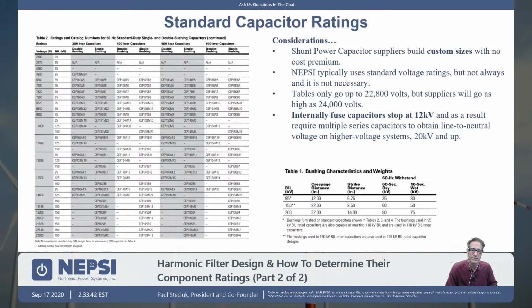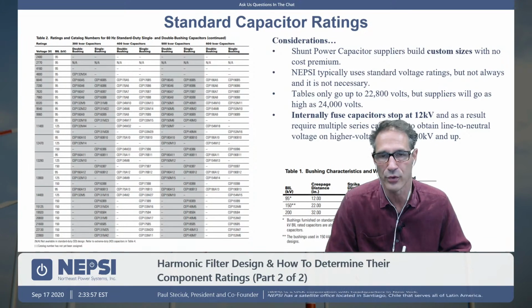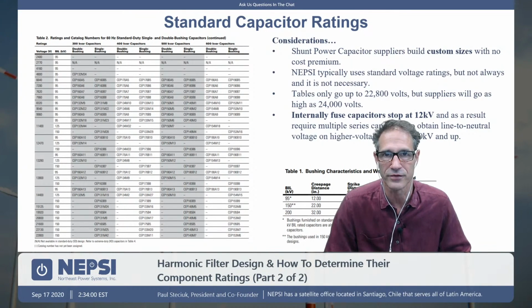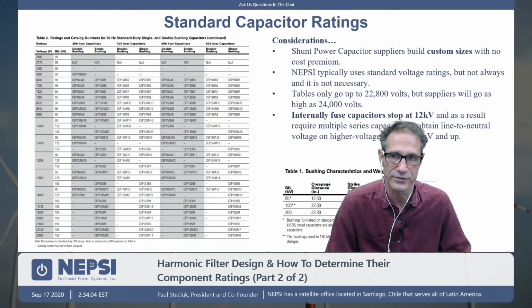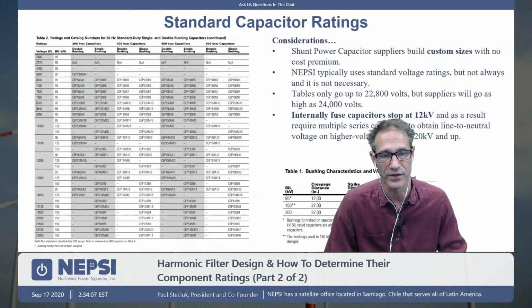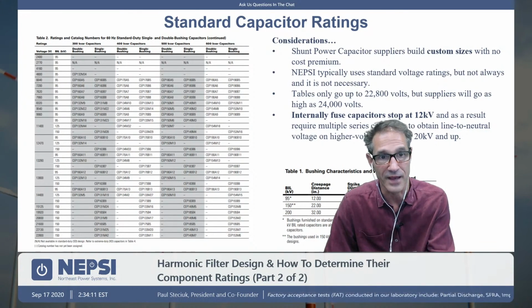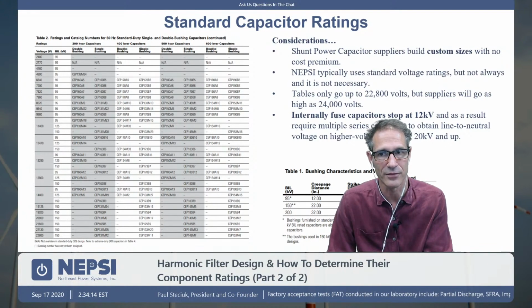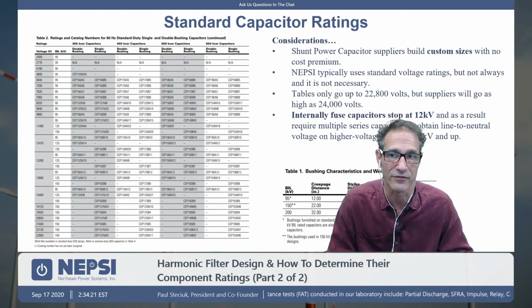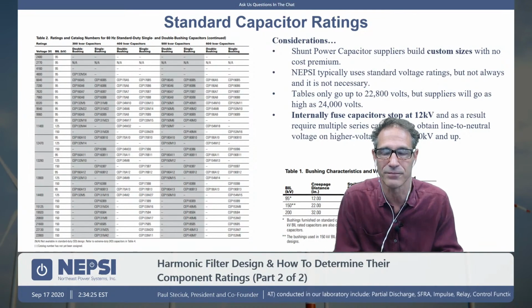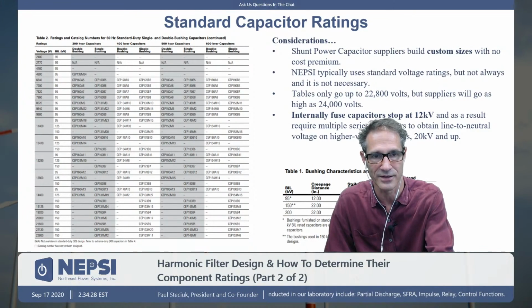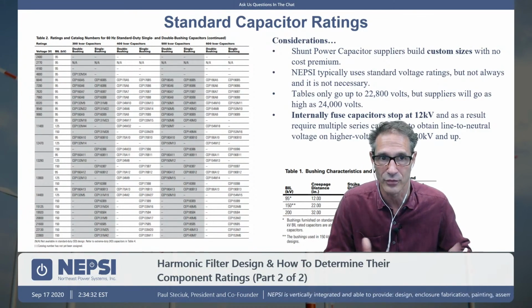Yeah, so good question. We do get requests from time to time for type test reports. I could tell you that if the capacitor has not been type tested, the one that's being specified, it does carry a significant cost for the type test. These manufacturers have type tested the various sizes of their capacitors, but if you actually want the exact capacitor that you specified, and harmonic filters are often going to an oddball rating, we might be going with, let's say, a 350 kVAR or 375 kVAR capacitor. The manufacturer may not have built that capacitor, so to ask the manufacturer for a type test on that specific capacitor can be very costly, on the order of $20,000.